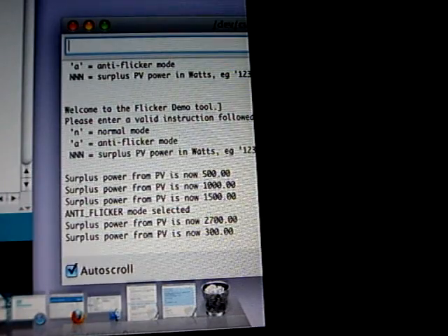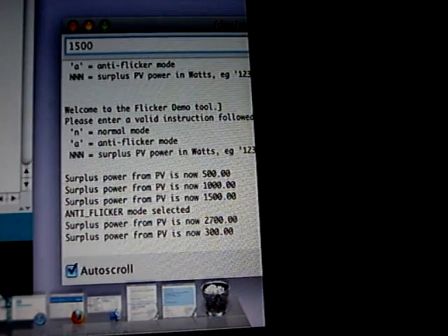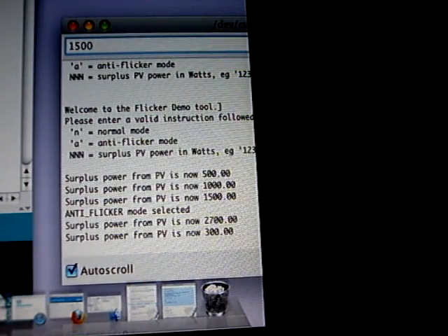So this to me doesn't look unpleasant flicker. Yes, you would be able to see the lights come on and off a little bit, but that's no different to when somebody puts on a kettle or jumps in an electric shower or whatever. So I'm pretty convinced that the most significant frequency or situation we're going to have to deal with is the half power rate.